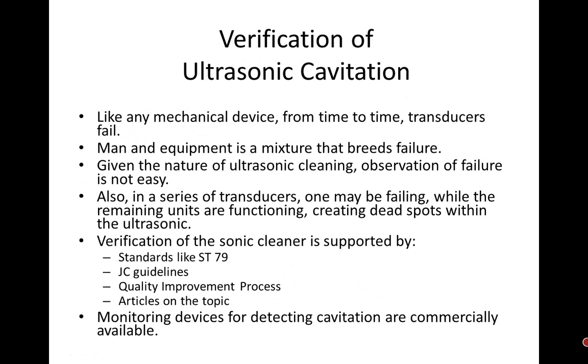Verification, like any mechanical device, from time to time, transducers will fail, and I'm going to show you that. Man and equipment is a mixture that breeds failure. When you put man and machine together, failure is going to happen. That is why we have quality processes, monitoring, quality steps along the way to make sure we're doing it. Given the nature of ultrasonic cleaning, observation of failure is not easy. Just hearing it making a sound is not enough, or seeing some ripples in the tank. That is just not enough. Also, in a series of transducers, one may be failing while remaining units are functioning, and they can cover it, but after a point, if you lose one or more, you will create dead spots within the ultrasonic tank. And if that's taking place and you don't know it and you put those instruments in there, they will not get as clean as you expect them to be.